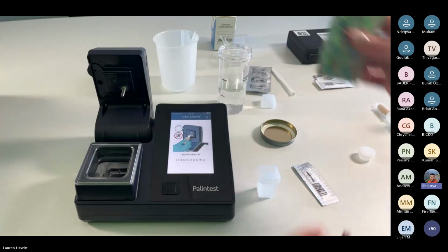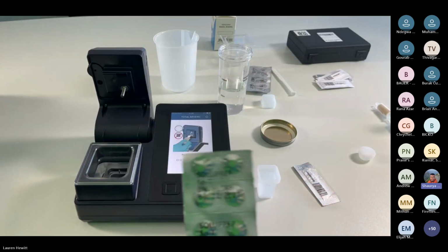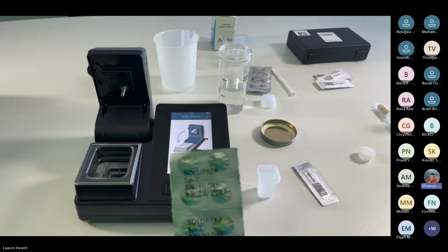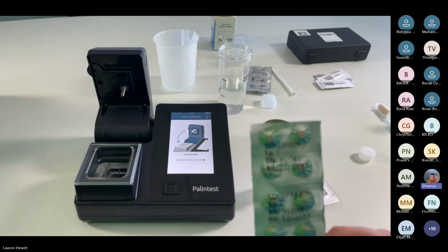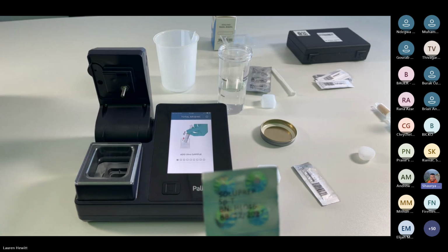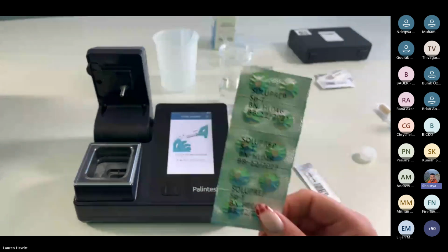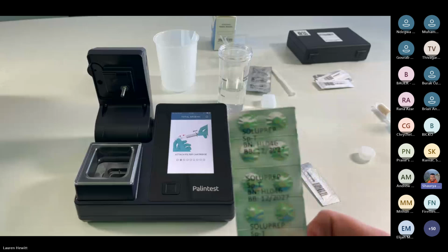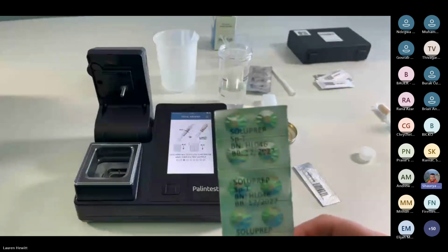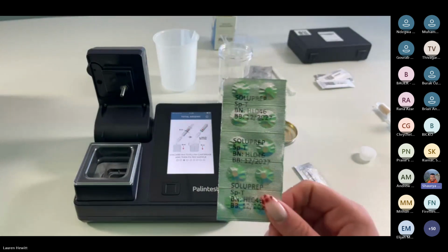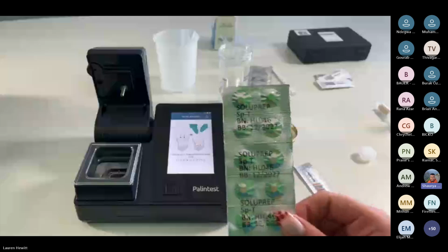We want to use the SPT tablets. These are a buffer tablet that ensure that the condition of the sample is at the correct pH for this testing. There is also a correct sample pH before preparation. For arsenic testing, the sample pH should be between 3 and 7, because anything outside of this, the buffer tablet only has a certain capability to bring it within that.